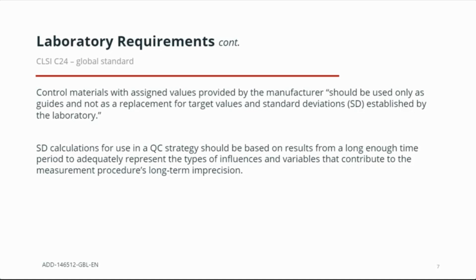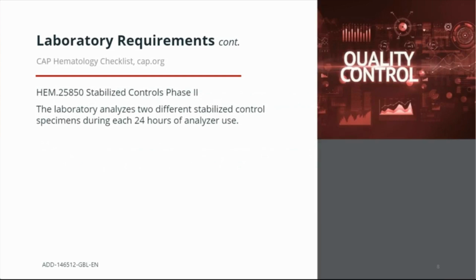So where a measurement procedure may not be providing us reliable results, we want to make sure we have those checks in place to detect that. Hence, the manufacturer values become guidelines once again, and the laboratory implements hard upper and lower limits with corrective actions to take when those limits are exceeded. The CAP hematology checklist was also recently updated in October 2022.